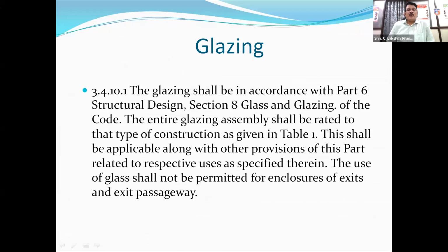Then glazing, this is one of the important things, as all modern buildings are using a lot of glass where the glass facade is being used. In such cases, if they are not properly protected, or if they are not provided with openings, for every 15 meters, a 1 meter opening has to be given for venting of the smoke. And if that is not given, in no time, the entire building envelope will be filled with smoke. And, as I told you, between the wall that we are using for this facade purpose and the actual roof, there is a gap. That gap has to be protected by providing fire sprinklers.